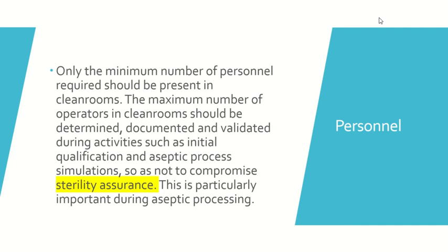As I'm saying, the personnel should be well trained, their practices should be observed and monitored, and finally certain qualifications are required whenever we are going to include personnel for any kind of aseptic process handling. So they are required to undergo media fill, where that person and their activity will be qualified. Majorly, challenge with the maximum number of persons in your facility, and try to use as few as possible during your routine process. That is the way we handle personnel qualifications.